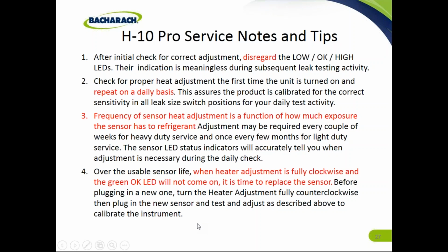So, as I said before, when you're using this unit, how are you going to find that you have a leak? The indicators are in the lights in the probe. That's the only light you're going to be looking at to see if you have a leak. It's at the tip of the probe. It's a red LED, and you also hear a faster ticking rate. So that red LED will start flashing faster, and the tick rate will go faster. Anything on the display panel, disregard. Those have nothing to do with finding the leak.